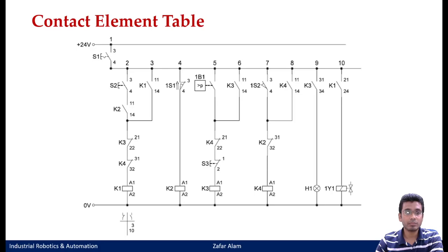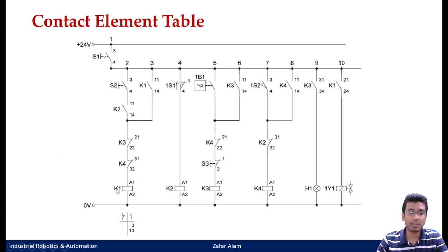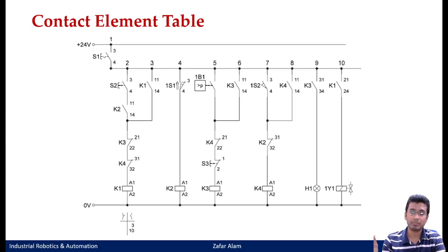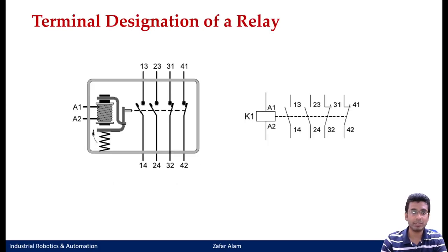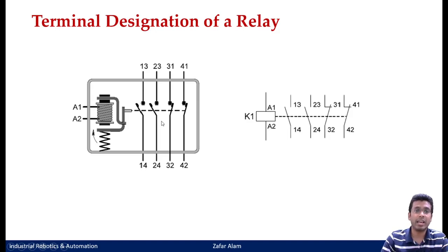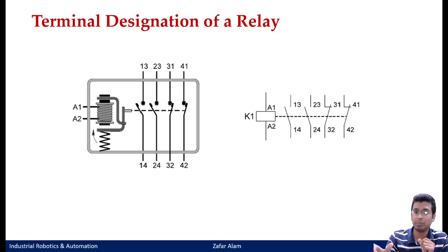When K1 is energized — the student asks whether there are two K1s and which one comes. The contactor K1 is only one, but there are two contacts. When the relay is energized, if suppose K1 has 10 make switches associated with it, the moment this relay is energized, all 10 will get energized at the same time. Once this element is pulled, all your normally open contacts will close and all the normally closed contacts will open simultaneously. Irrespective of how many contacts — if there are 30 contacts of a single relay K1, all 30 will get actuated at the same time.